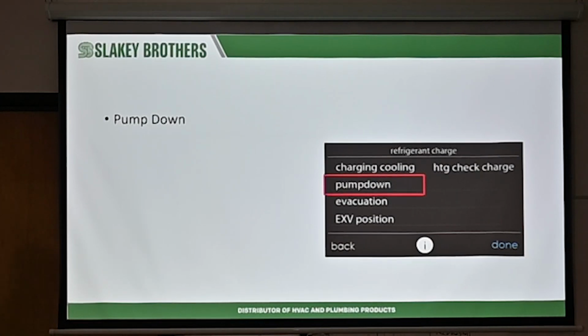Let's say you forgot to do a long line set solenoid and you want to trap all the refrigerant in the outdoor unit, you do a pump down. It'll pump down automatically for you. It does all the work, and then it'll pump down as far as it'll go, and then you close the valves off and you recover a pound or 2 pounds at the most. Makes the job a lot quicker. Instead of having to recover 15, 18 pounds of refrigerant, now you maybe only have to recover a couple pounds. So that's what the pump down feature is for.